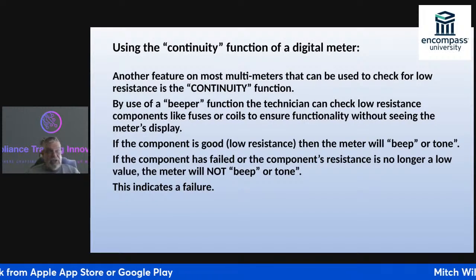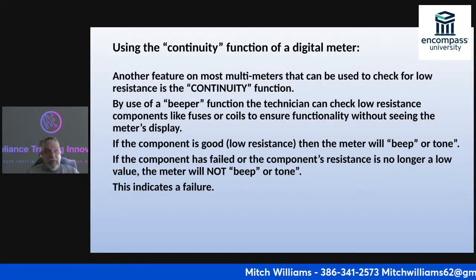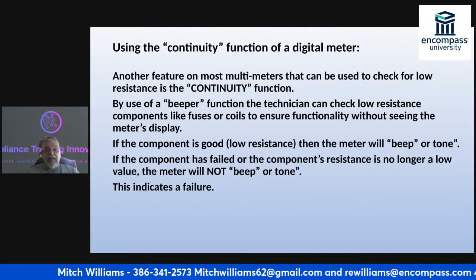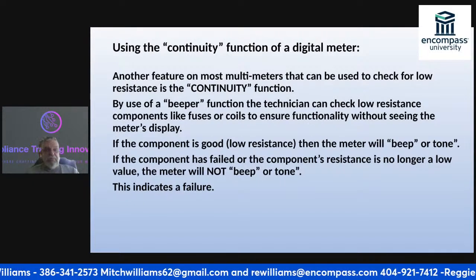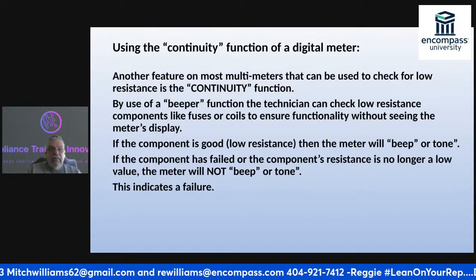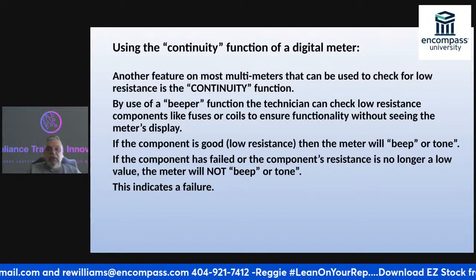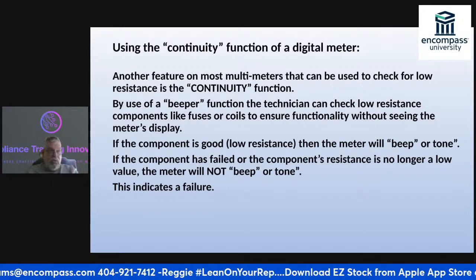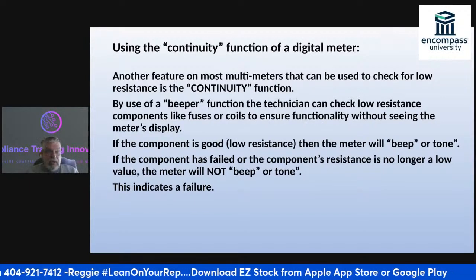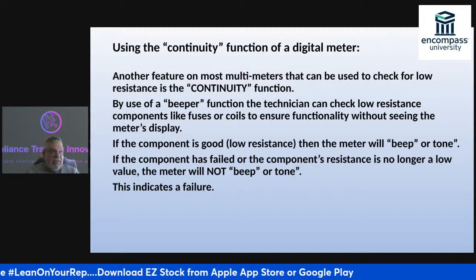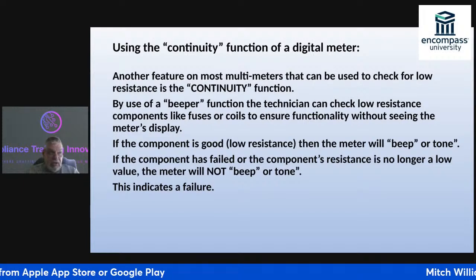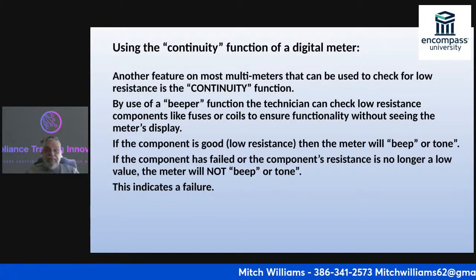Like I said, I can check a compressor by going from the common to the open, common to the start winding, and the common to the run winding. So all I'm doing is completing the circuit. That's all that I'm trying to do. That's what the continuity function does. The nice thing about the continuity function is I don't have to actually be looking at the meter. The meter will actually tell me it's good by giving me the tone. Or if I don't get a tone, I know that it's bad.